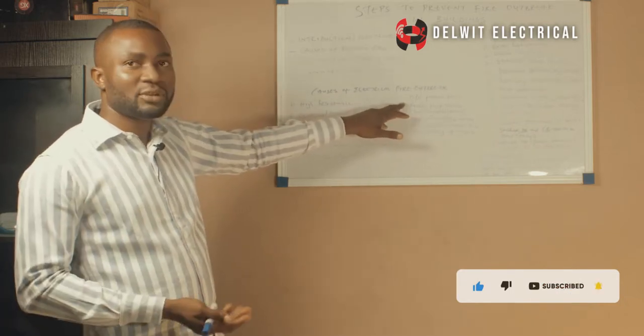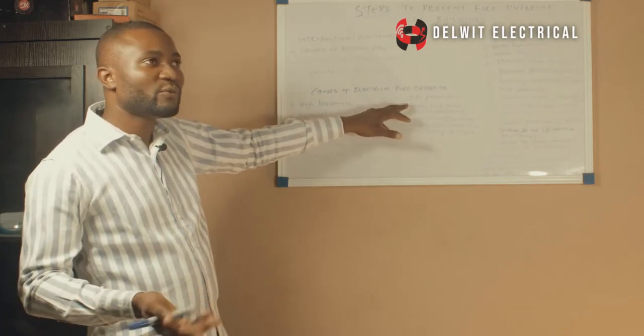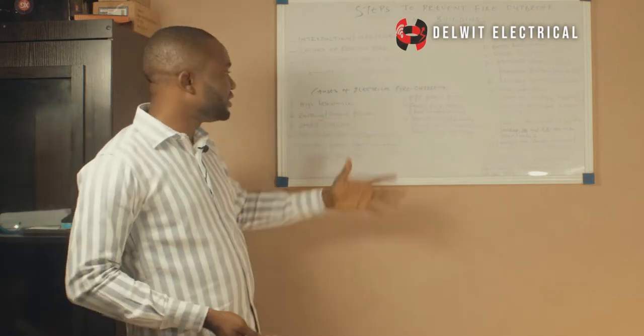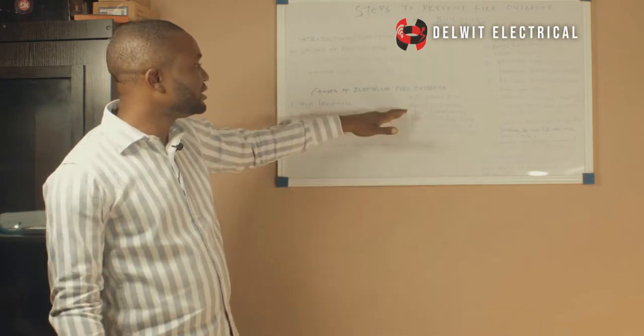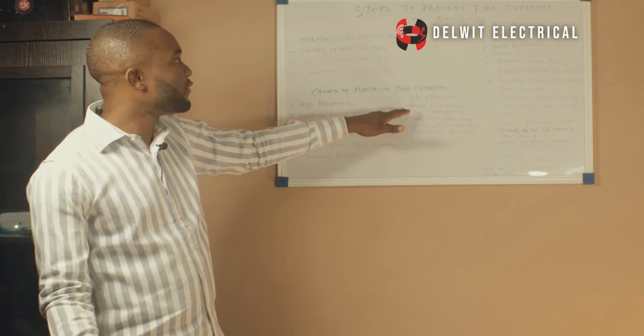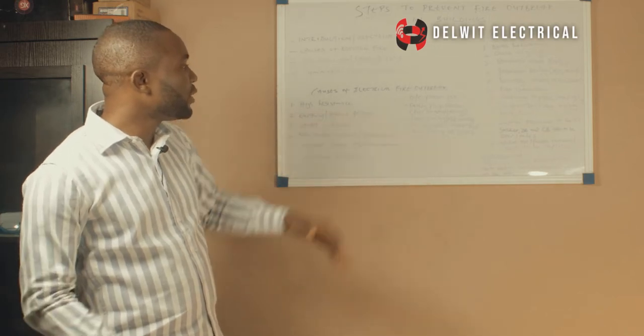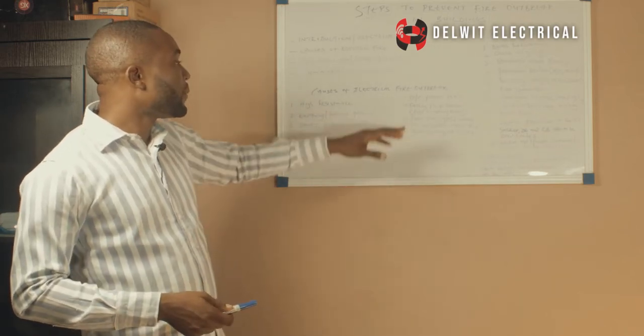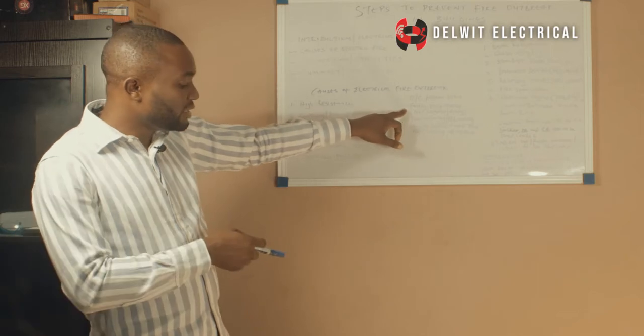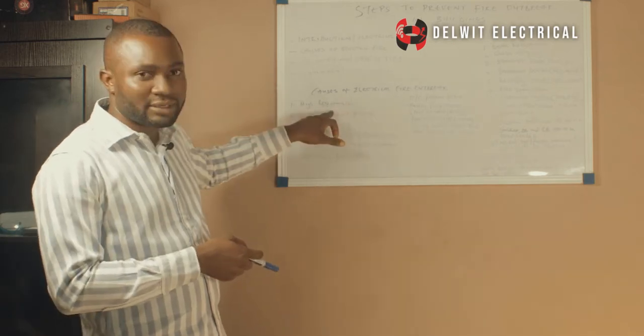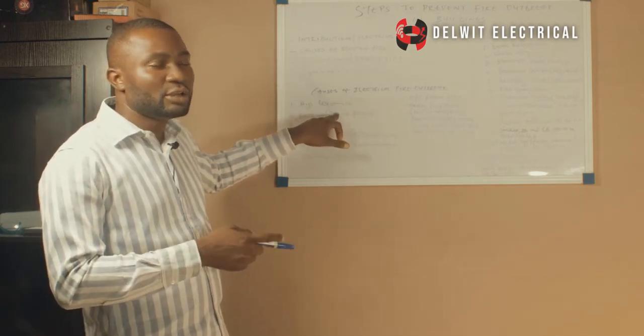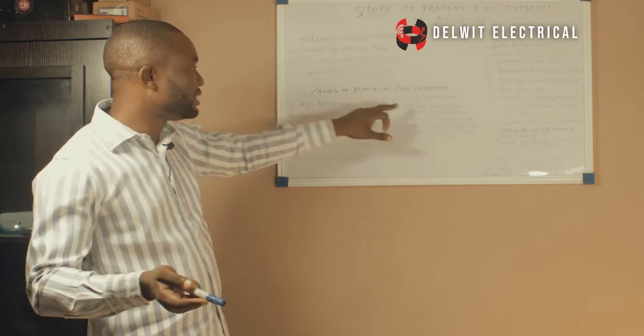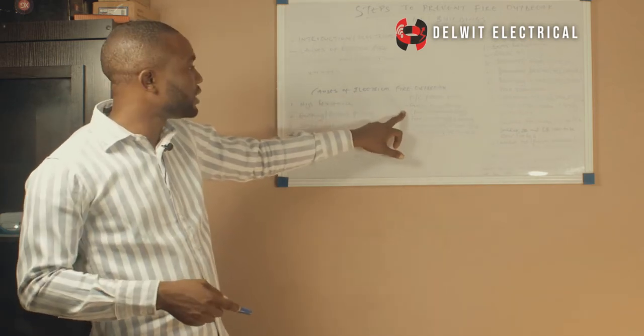let him change the sockets. Sockets are not expensive. The maximum you could get is 1.5, so you could get that for 500, 600. So please try and change it as fast as possible to prevent fire outbreak. The third point is poor wiring. Now, this arcing leads to high resistance, and that high resistance does not have an outlet, so it will damage the equipment that is connected to that port.